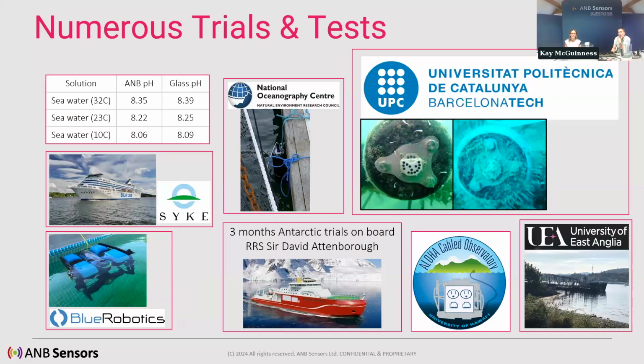Uniquely, we generate a small amount of peroxide during our measurement sweep, which allows us to keep the transducer surface, our monitoring surface, clean. The peroxide breaks down easily in water, but it's enough to keep it clean, and therefore we have anti-biofouling built into the sensor. Just to be completely clear, both sensors were down for the same amount of time at the same place. One was switched on and one was switched off. By having it switched on and doing our measurements, we can keep our transducer clean from any biogrowth. So it's a massive difference between sensors. Yeah.